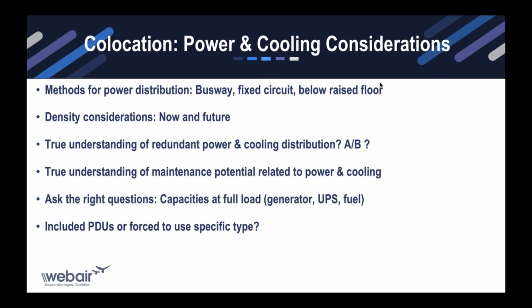When it comes to A and B redundancy, or N+1 or 2N for power and cooling, the devil's in the detail. On the client side, I've taken so many tours over maybe 20-plus years where everything's redundant, everything's N+1—then a year later there's a surprise. All the CRAC units run off one set of pipes throughout the facility, one set of pumps, and the pump fails, so all your ACs start pushing out hot air at the same time. There's a lot of gotchas.